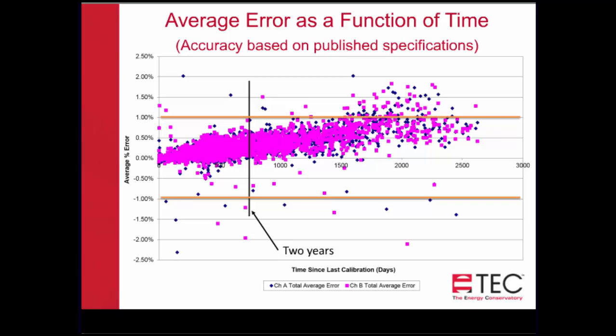So where did all this information come from? So here you can see in this chart, and you can see the two different colors. One is actually channel A and one is channel B. So on the far left-hand side of the chart, you can see that everything is very close to zero. And over time, and this is in the number of days, all the way out to 3,000 days, you can see that the pressure channels start to move away from zero, and for the most part, they tend to go in the same direction. And you'll also see that both channel A and channel B will also move together.